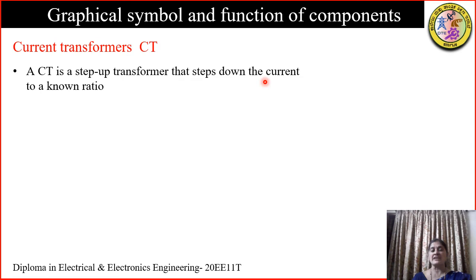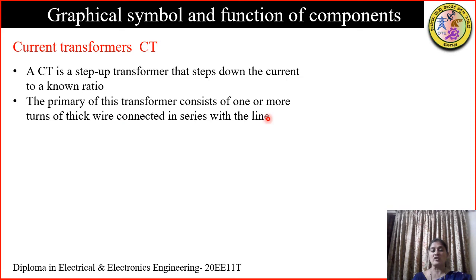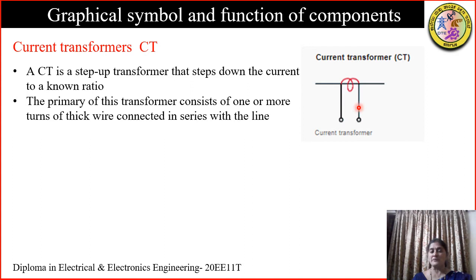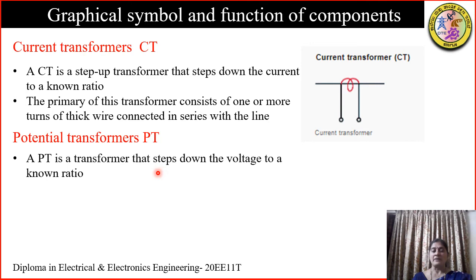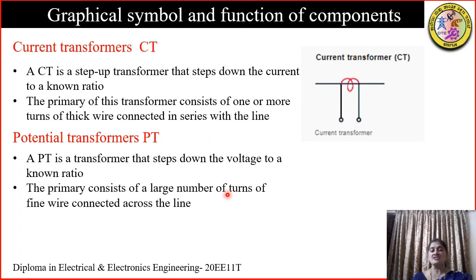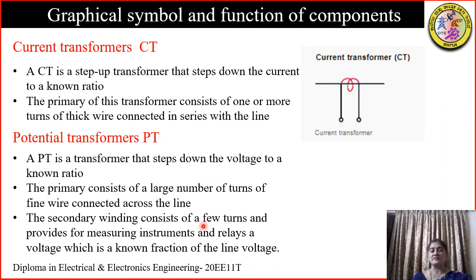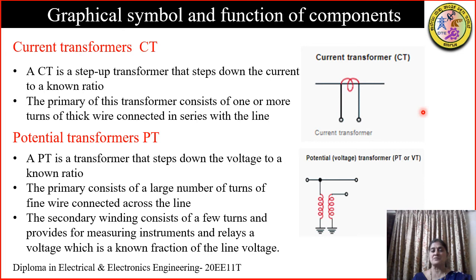A current transformer (CT) is basically a step-up transformer which steps up the voltage but steps down the current to a known ratio. The primary consists of one or more turns of thick wire and is connected in series with the line. The measuring instruments are connected across the secondary terminals. A potential transformer (PT) steps down the voltage. Its primary consists of a large number of turns of fine wire, and the secondary winding has few turns and is used to connect the voltmeter.